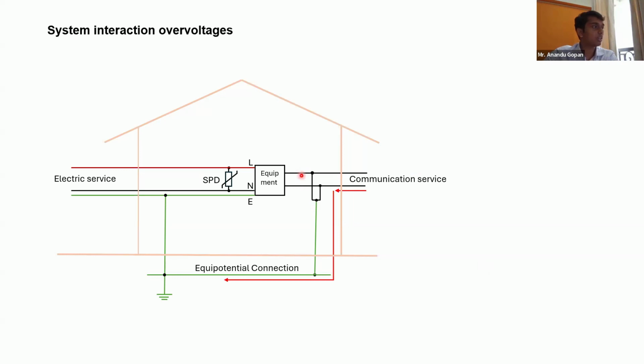Obviously, your SPDs at this region will divert the surge to your protective earth, and this is your equipotential connection. It can either be a PE conductor or your MET, whatever is connected, and this will be connected to a common point where your electrical installation is also connected. So the issue is, you can see there's a huge current flowing through this conductor.